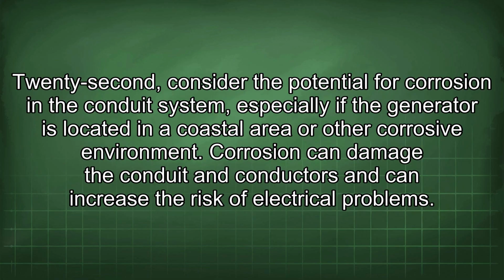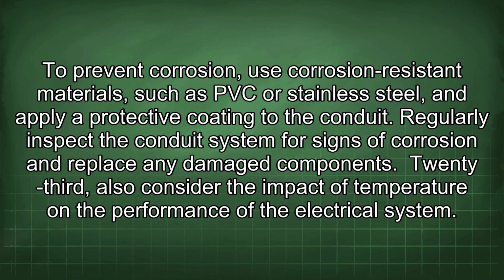22nd, consider the potential for corrosion in the conduit system, especially if the generator is located in a coastal area or other corrosive environment. Corrosion can damage the conduit and conductors and can increase the risk of electrical problems. To prevent corrosion, use corrosion-resistant materials such as PVC or stainless steel and apply a protective coating to the conduit. Regularly inspect the conduit system for signs of corrosion and replace any damaged components.